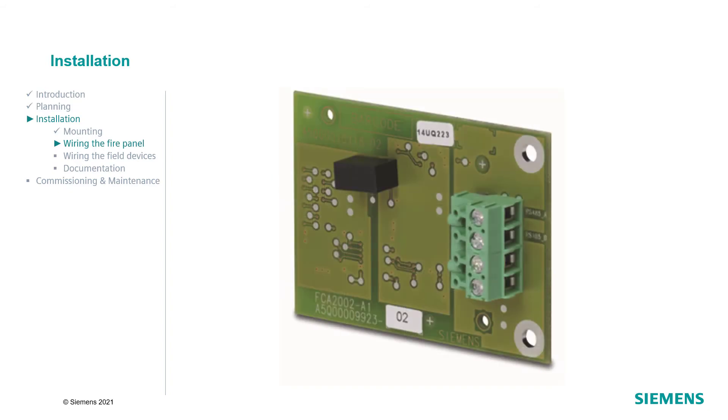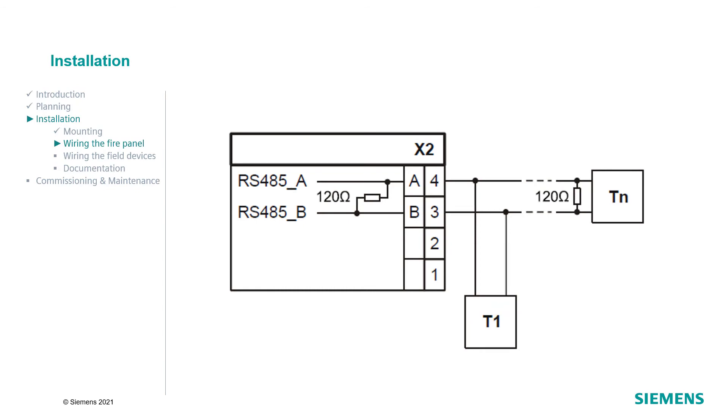If the RS485 is used, connect terminal 4 to the A line and terminal 3 to the B line from the RS485 module to the participant. Terminate the line after the last participant with a 120 ohm resistor and use shielded cables.